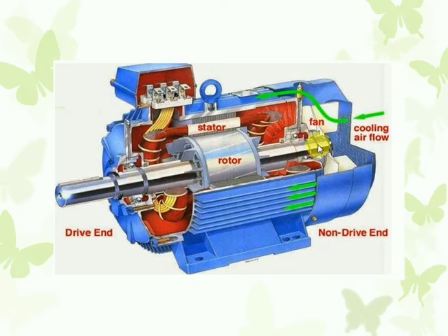And then we have the fan. The fan is in order to reduce the temperature of the winding. If we reduce the temperature, the resistance definitely will come down. So losses also will come down. So we have the fan to provide cooling in the enclosure. The atmosphere air will be sucked in by the fan and it will be discharged to the fins outside of the enclosure. So air will be blown off in that direction, and we can cool the heat dissipation.